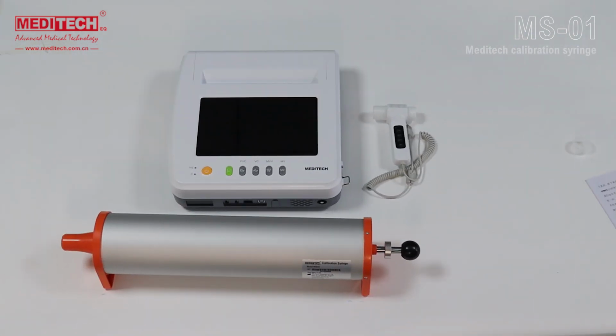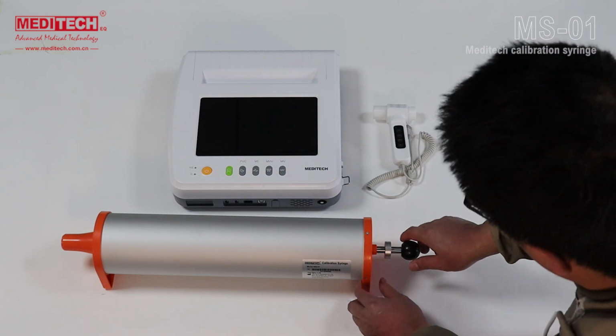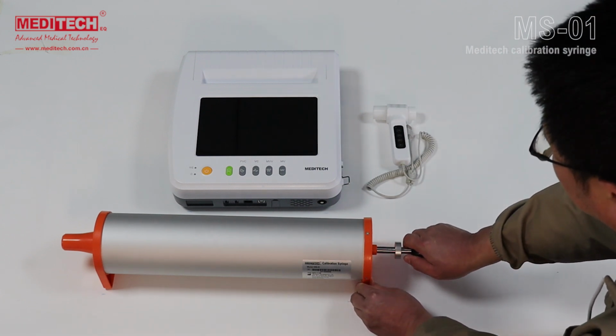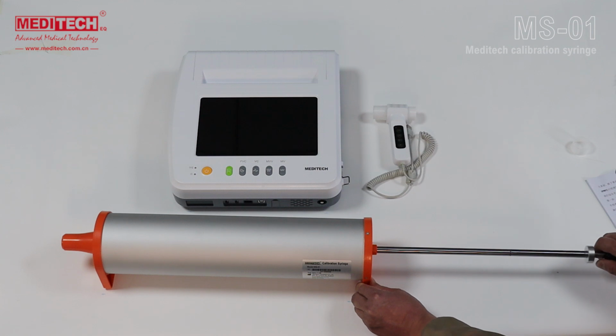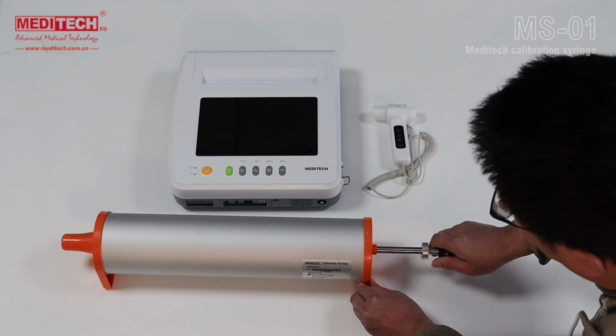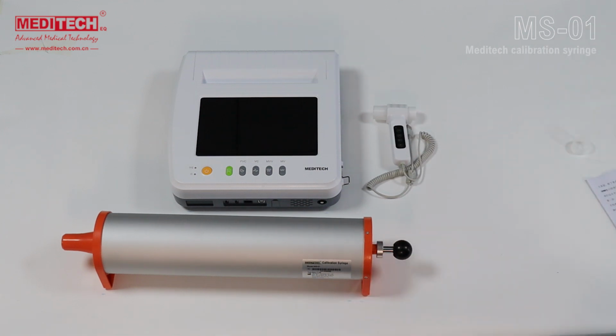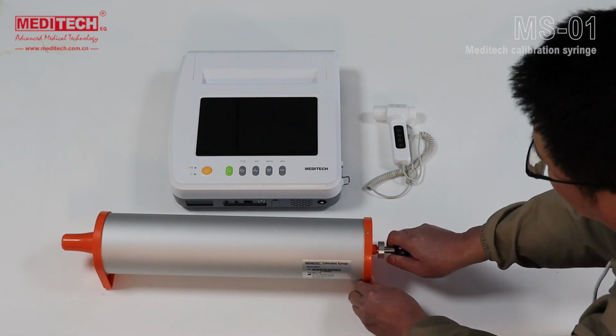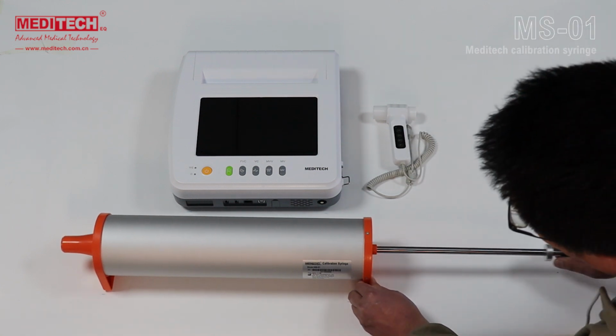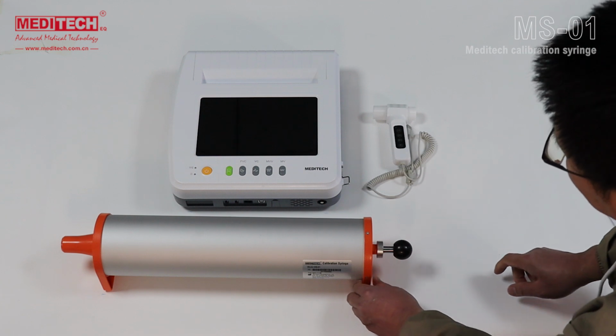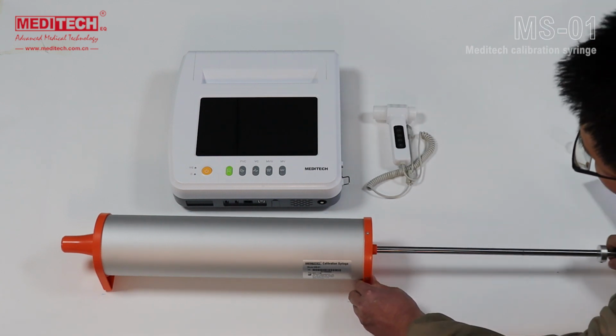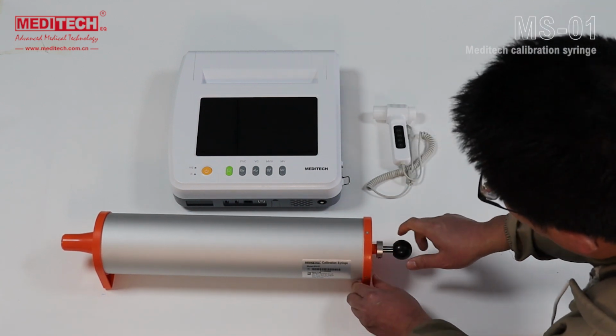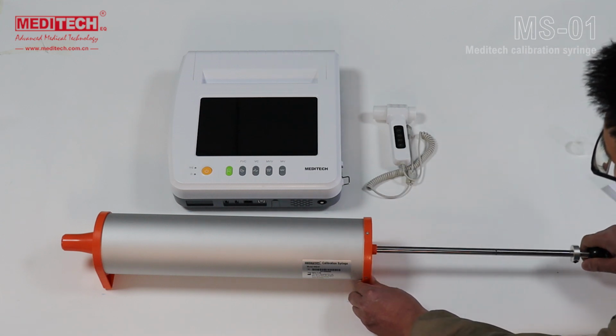Carry out the push-pull process in 3 cycles for calibration. The first cycle is at low speed, about 3 to 5 seconds. The second cycle is at medium speed, about 1.5 seconds. The last cycle is at high speed, completing the push and pull within 1 second.